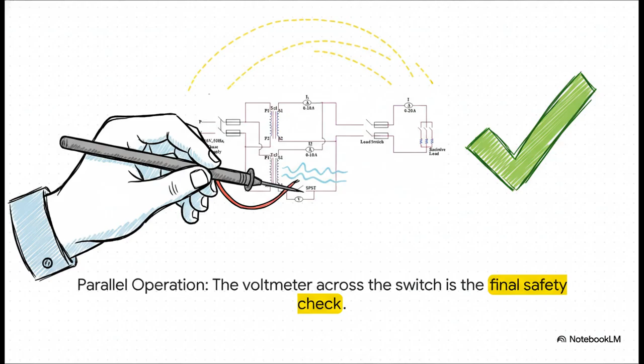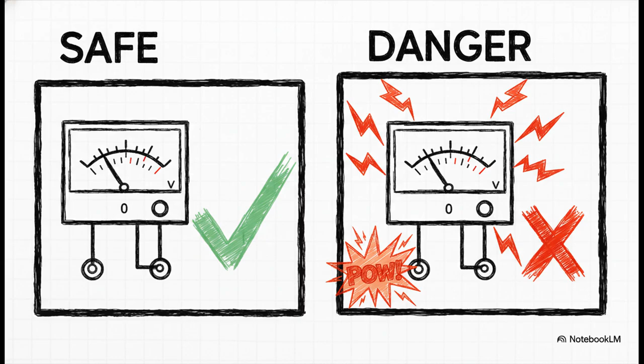So when you're connecting them, as you see in this diagram, there is one final, absolutely critical safety check. An engineer will place a voltmeter right across the terminals of the final switch before they even think about closing it. That one little meter reading, that's the moment of truth. If that voltmeter reads 0, it means the transformers are perfectly in sync. They're pushing in the same direction. You're golden. It's safe to close the switch. But if it reads anything other than 0, especially if it reads double the rated voltage, that means the polarities are reversed. They are fighting each other. Closing that switch would create a massive explosive short circuit. It's the one check you can't get wrong.